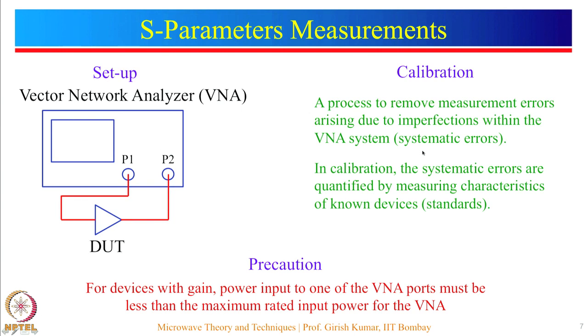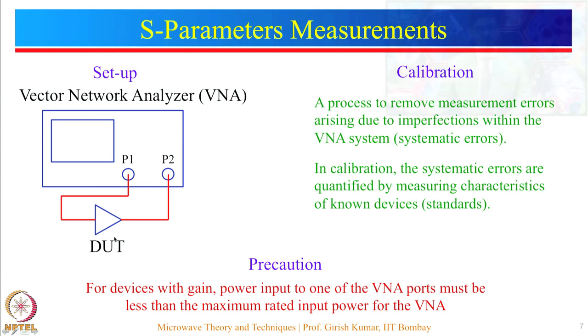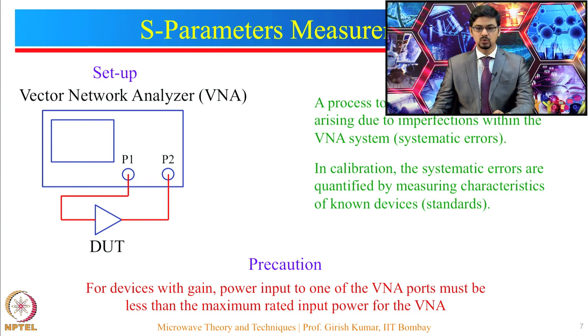During the calibration process, systematic errors are quantified by measuring the characteristics of known devices called absolute impedance standards. Once these quantified systematic errors are known, they can be adjusted in the actual DUT measurements to give more accurate results. We will see how to do the calibration process and how to measure S parameters in the practical part of this lecture.